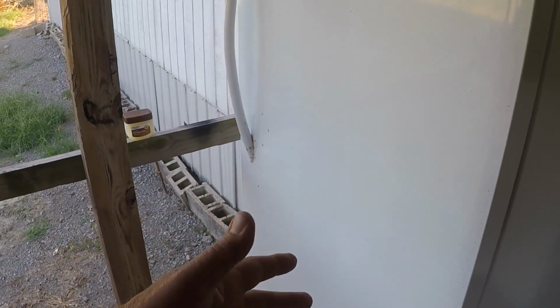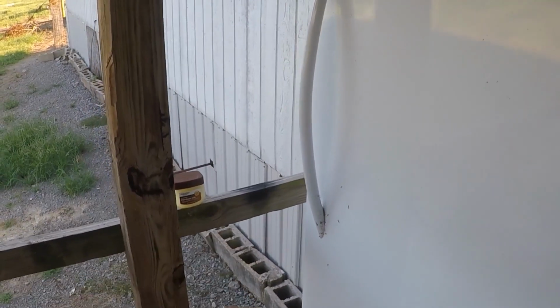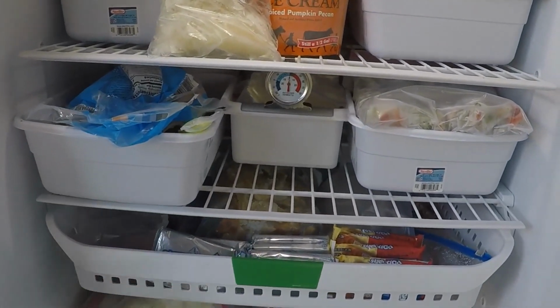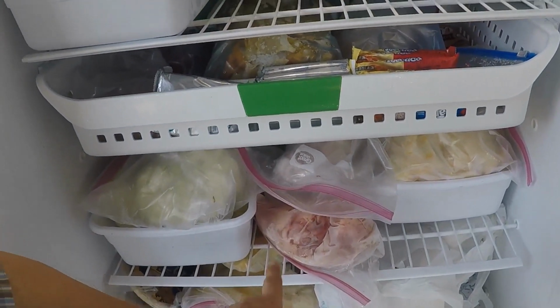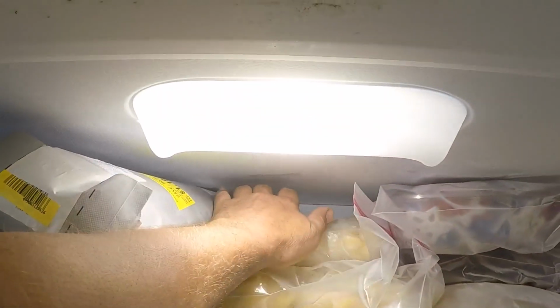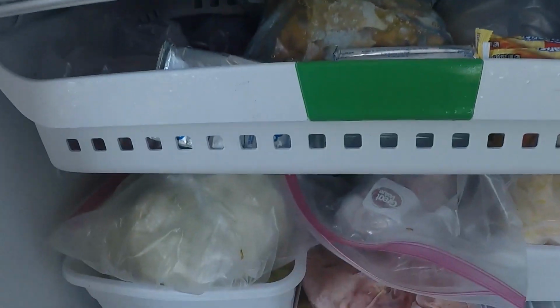It's all automatic, but sometimes your box will quit cooling. And the reason is that that clock has gone out or the heater has gone out and it's no longer defrosting. And you've got to be able to get air circulation on an upright. On chest freezers, they do not have a fan inside. But this one down here in the bottom has a fan, and it has ductwork that comes up. And right up in here, if you could feel this, there's cold air blowing out. And the idea is, this cold air blows down, recirculates, and keeps this all cool.